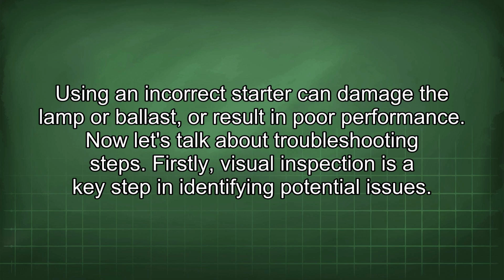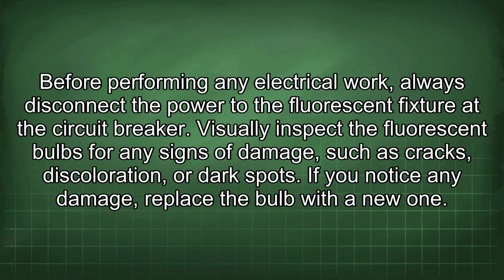Now let's talk about troubleshooting steps. Firstly, visual inspection is a key step in identifying potential issues. Before performing any electrical work, always disconnect the power to the fluorescent fixture at the circuit breaker. Visually inspect the fluorescent bulbs for any signs of damage, such as cracks, discoloration, or dark spots. If you notice any damage, replace the bulb with a new one.